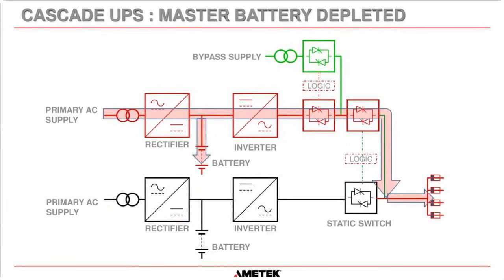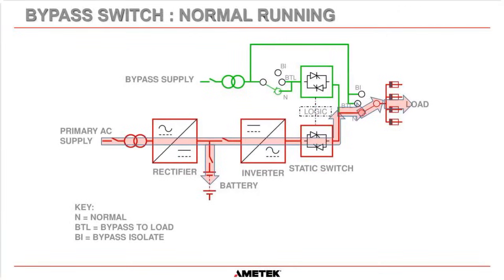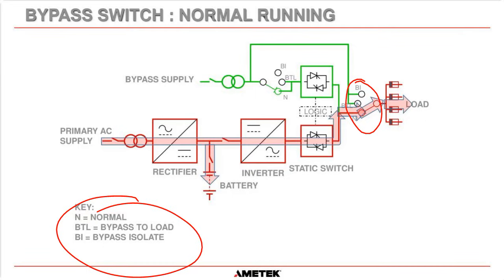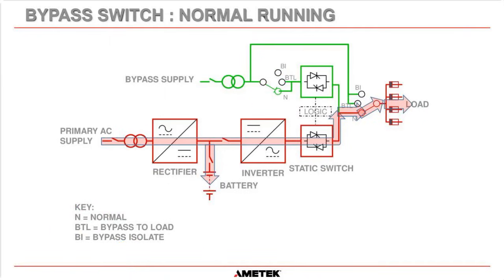Okay, so now we're going to talk about bypass switches, which can get confusing because I think the most common misconception out there is the difference between a static switch and a bypass switch. So we've got a key down here. We've got our bypass switch. There are contacts here and contacts here, and they are labeled N for normal, BTL for bypass to load, and BI is bypass isolate. These are the names that we give to the positions on an AMETEK bypass switch. Some other manufacturers use different labels for their positions.